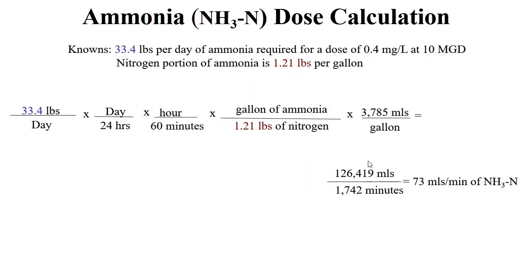Similar to earlier calculations, everything is the same except we have 33.4 pounds per day in the numerator and 1.21 pounds per gallon in the denominator. We cancel pounds, days, hours, and gallons, leaving mL per minute. 33.4 times 3,785 gives 126,419 in the numerator; 24 times 60 times 1.21 gives 1,742 in the denominator, resulting in 73 mL per minute of ammonia as nitrogen to feed 0.4 milligrams per liter at a plant operating at 10 MGD.